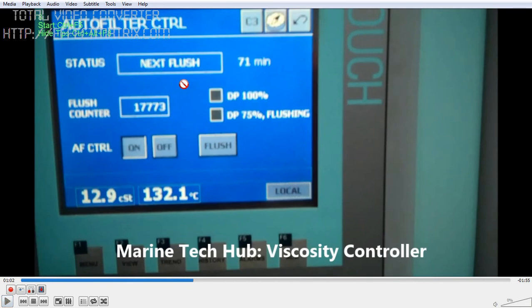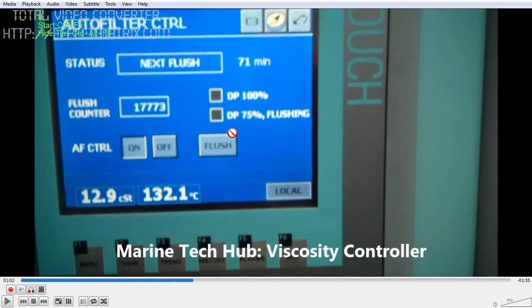This is the flushing cycles. You can see right now 71 minutes is remaining for the next flush. Flashing means the auto filter will be cleaned. We normally set it at 120 minutes — 2 hours. Then we have a DP at 75 percent, which is the differential pressure. If it reaches 100 percent differential pressure, you will get an alarm. You can also manually backflush the filter — if you press the flash button here, it will start backflushing.